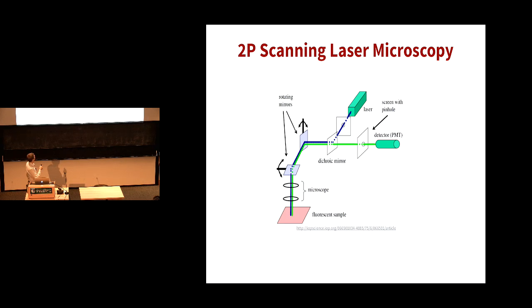This then goes back through these rotating mirrors, hitting our detector, a photomultiplier tube in this case. So we sweep this back and forth over time, and we can do this extremely rapidly using state-of-the-art resonant galvanometers to achieve frame rates of about 30 hertz, or even higher if we limit our field of view. So you can do this quite rapidly, and there are trade-offs between how much tissue you're looking at and how fast you can revisit those areas.